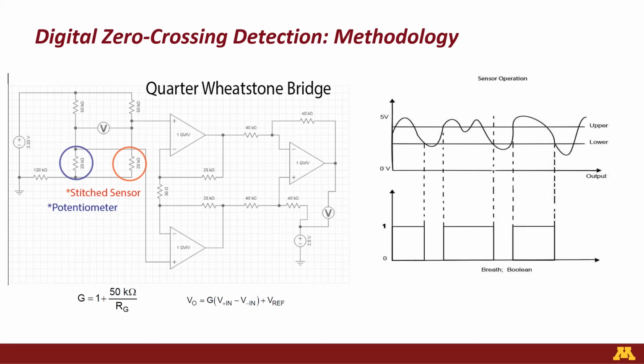When the signal is seen, a lower threshold and a higher threshold are noted, indicating a low voltage and a high voltage reading. The difference between the thresholds is where a breath is counted, but only when both thresholds are crossed. Digital zero crossing can save energy and be a simpler computation than a fast Fourier transform, allowing for a more accurate monitoring of respiratory rate.